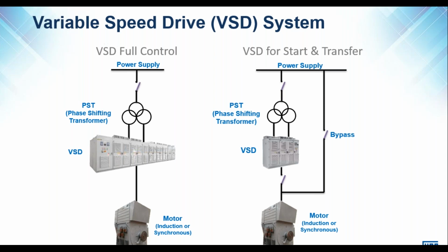However, we do have the option, and this is possible if you want to use the VSD only for starting, and it does not need to be permanently connected to the machine. So we are able to start a machine with the VSD and bypass the VSD. So the VSD can be provided with a built-in synchronism card or sync relay that is able to synchronize the VSD voltage output with the supply voltage output, and we can do a bypass. In this case, there are a few milliseconds where both the VSD voltage and the supply voltage is applied to the motor before the VSD is taken out of the circuit.